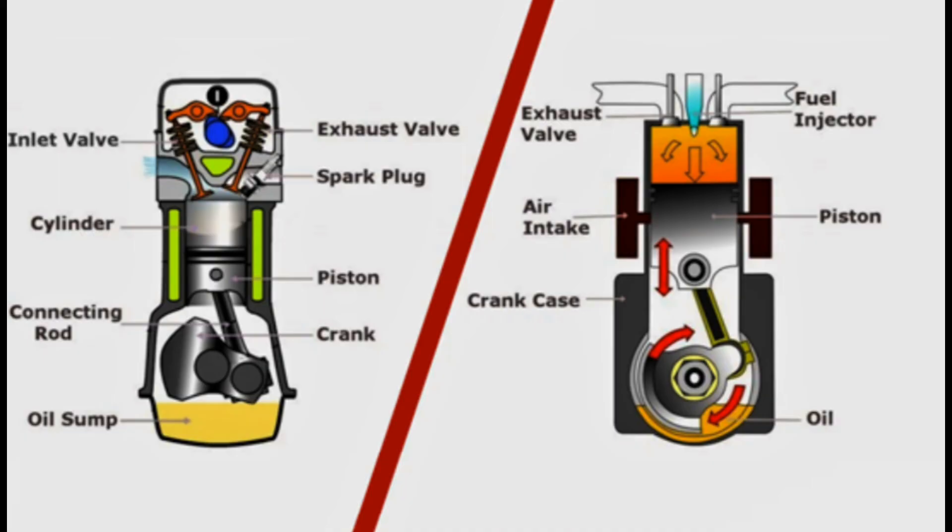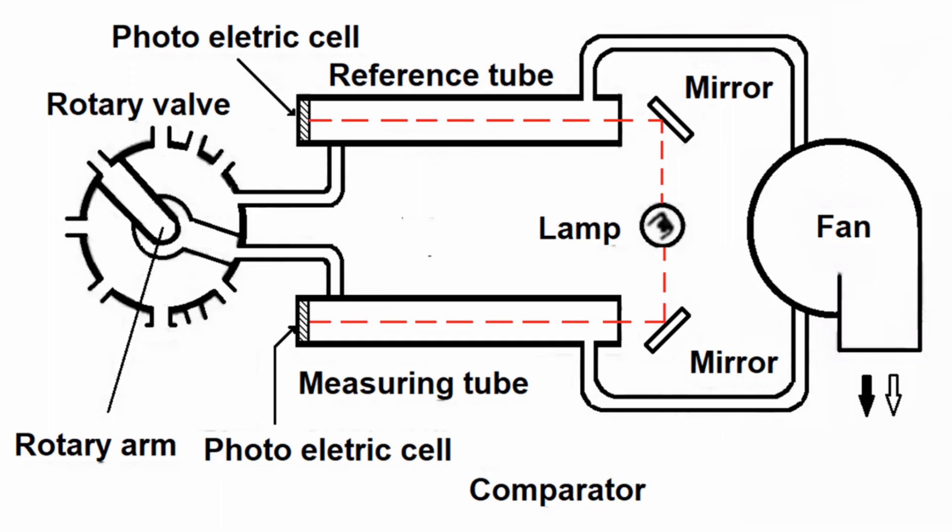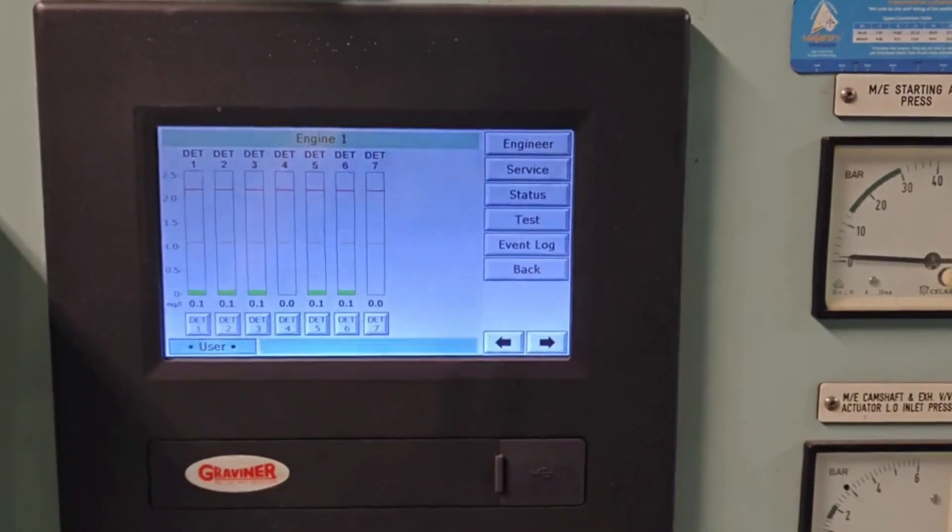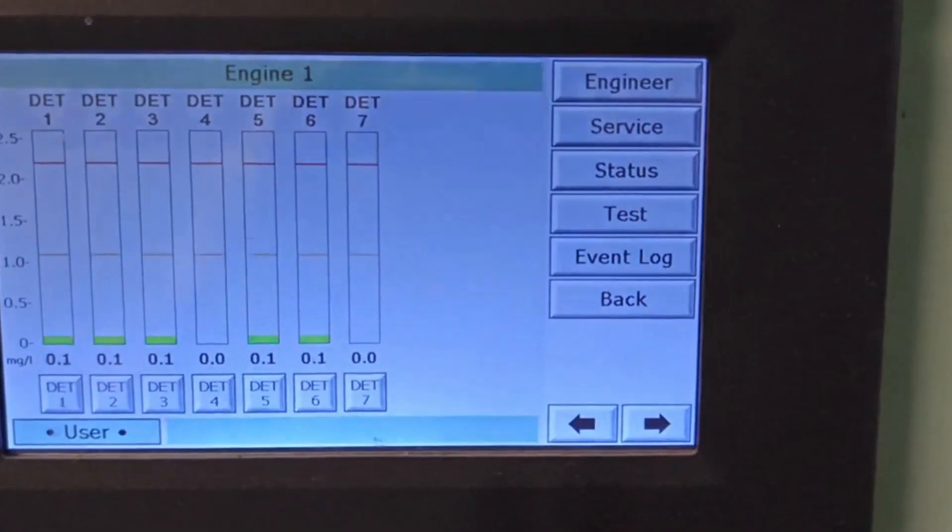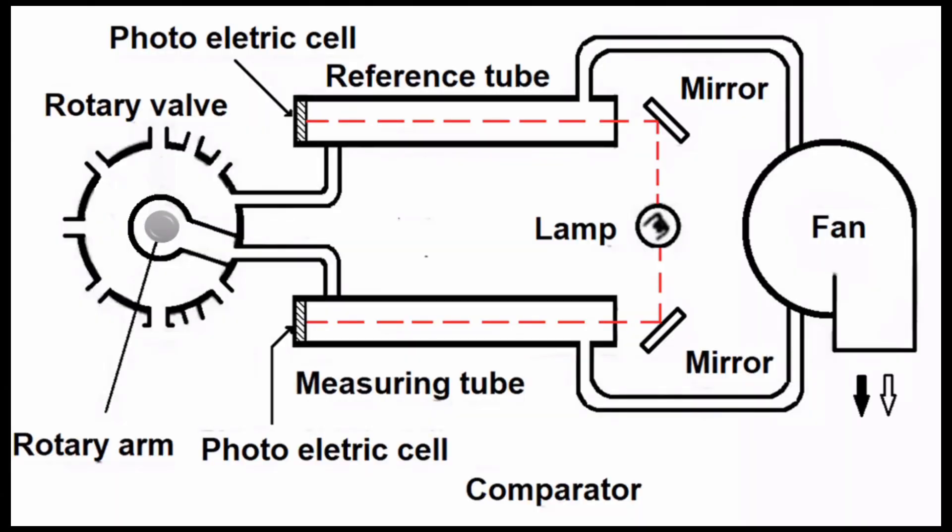It is important that this concentration of oil mist should be detected, thereby avoiding explosion and damage to the engine. This role is done by an oil mist detector that is OMD. It will detect the oil mist from individual units and raise the alarm. Crankcase of each cylinder is connected to the OMD which continuously checks the air sample from each cylinder.